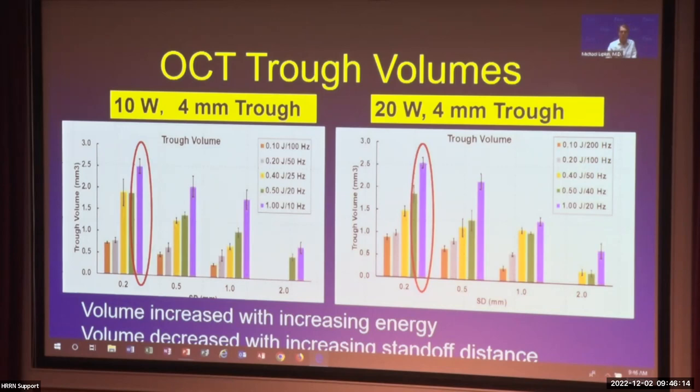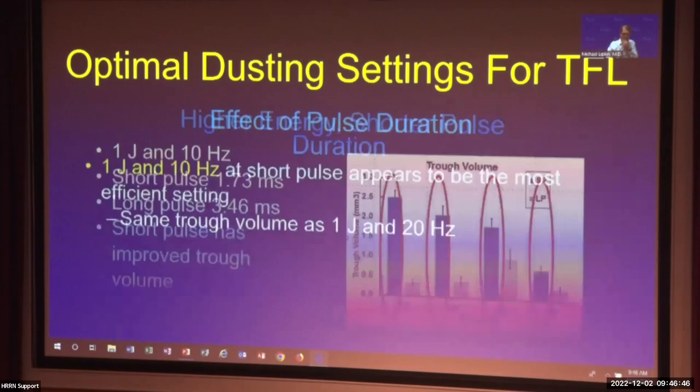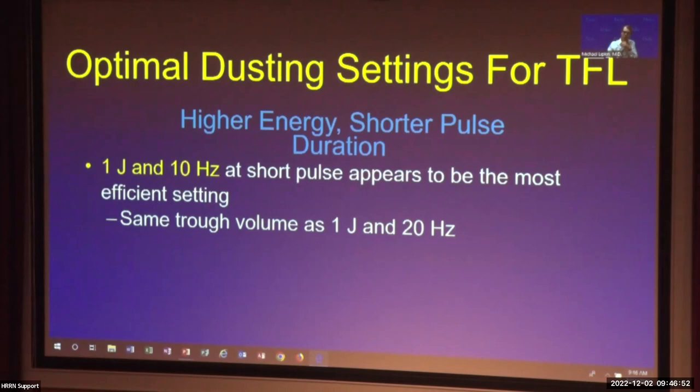Volume increased with increasing energy. For pulse duration effects, unlike holmium where long pulse modulation is more efficient for dusting, for thulium we looked at whether short or long pulse would be better. The pulse durations are much longer than holmium — short pulse is 1.73 milliseconds and long pulse is 3.46 milliseconds. Across the board at different standoff distances, short pulse is more efficient. So 1 joule at 10 hertz with short pulse appears to be the most efficient and probably safest setting for thulium.